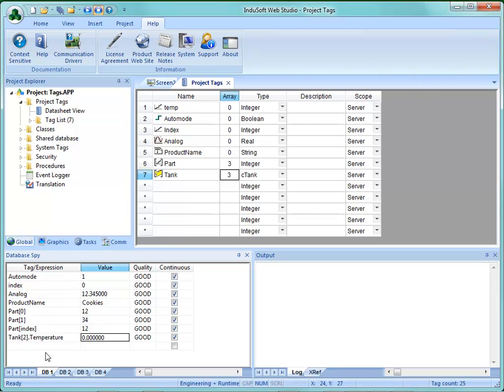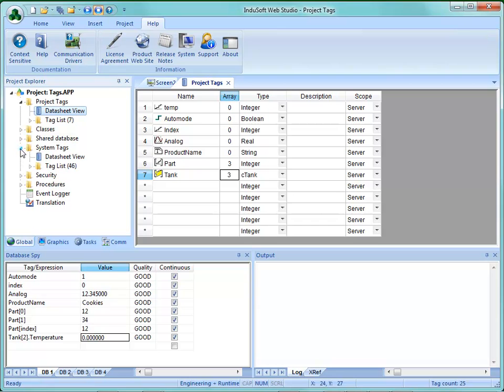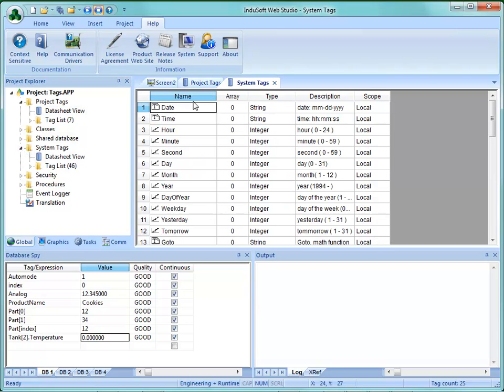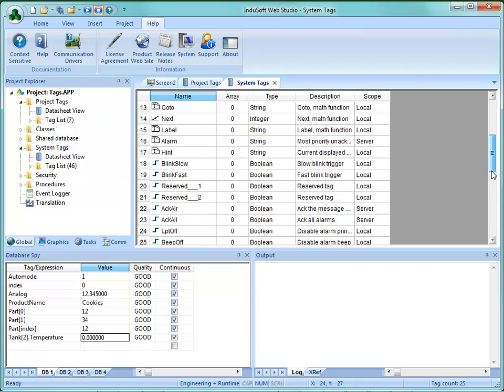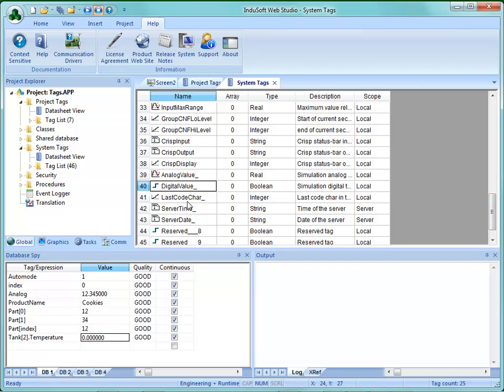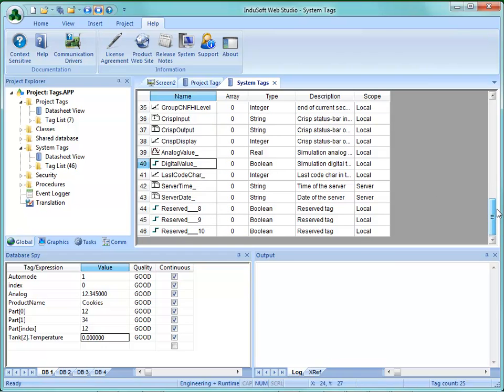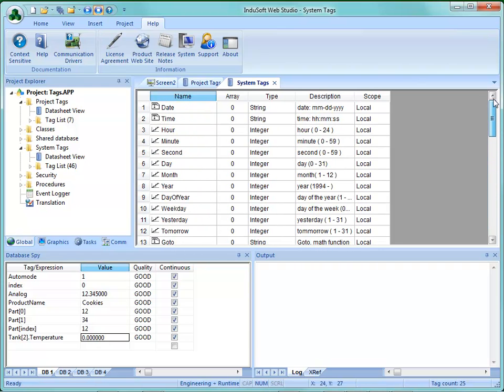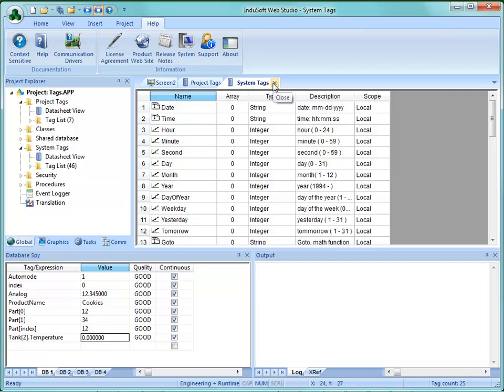The tag count is for project tags you've created and does not count your system tags. Opening the system tags datasheet view, you'll see things like date, time, hour, minutes, second, and so on. There's also BlinkSlow and BlinkFast, which toggle at 600 milliseconds and 200 milliseconds, and some simulation tags — AnalogValue and DigitalValue — which you can use for simulations. These system tags do not count against your tag count.